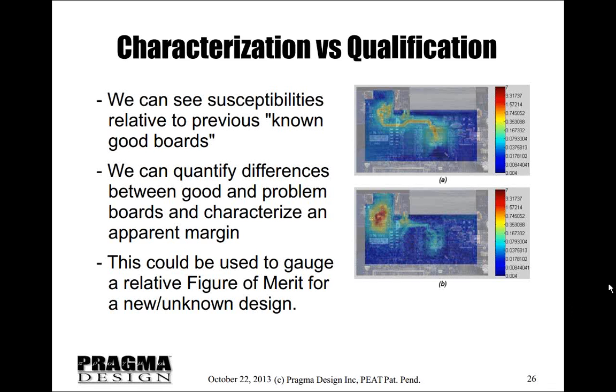Richard asks, the example you show is on the board level. Can it also be used to scan on the chip level, and what is the resolution? The resolution is dependent on step size, which the device we have can do in 500 micron steps, and then the probe geometry, which is related to its bandwidth. A smaller probe will resolve more detail, but it has a different bandwidth than, say, a 5 millimeter probe.